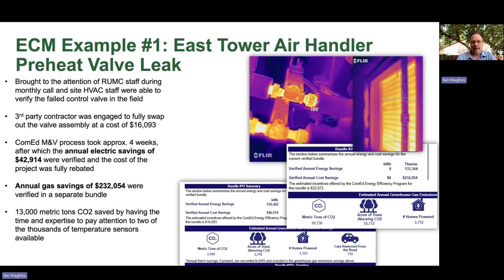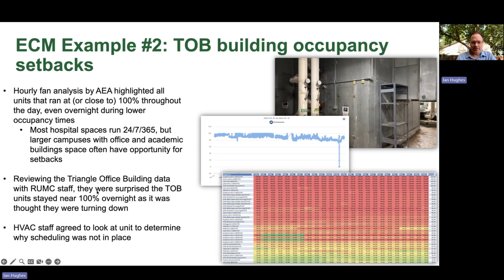There was an impression that there was a previously set up scheduling for those air handlers to turn off, turn down, or set back overnight. There's no need to have non-patient spaces running 24/7, 365. So they thought they had already implemented the schedule, but something changed or got switched up in the building automation system. We did some digging with AEA and found that it was not being turned back overnight at all, and was on 100% of the time.